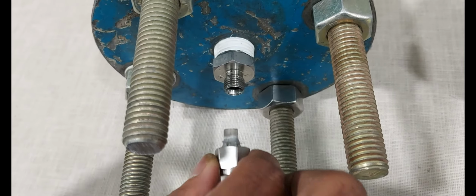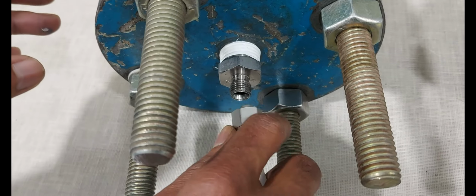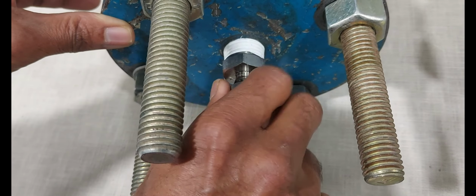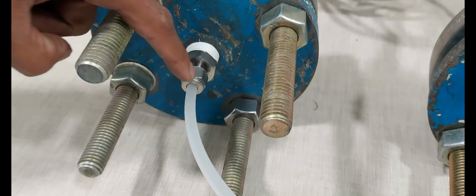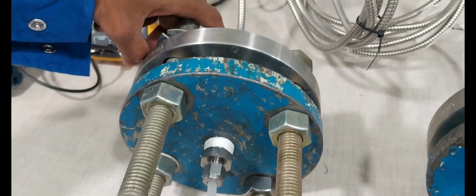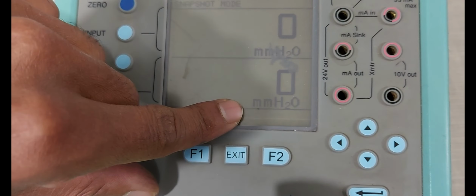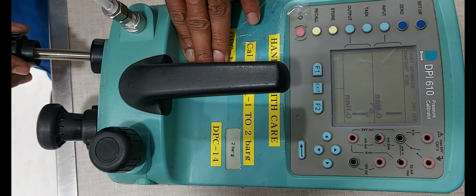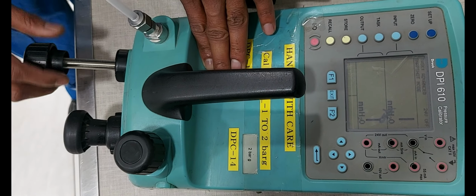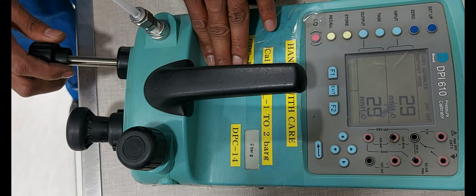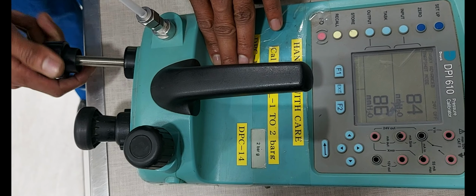Next we are connecting the high side only. Okay, we are connecting the high side at the flange. Tube high side is connected. Next close the pressure calibrator vent port. Unit is mmH2O. Next we are applying the pressure. Now we are starting the pressure.